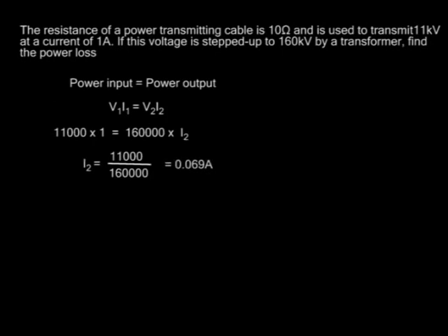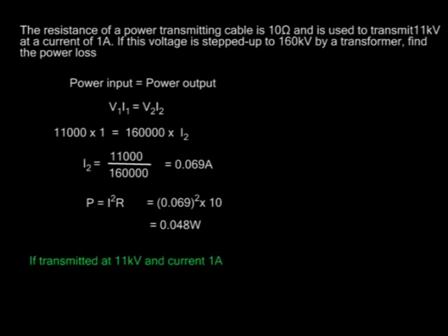That gives us 0.069 amperes. Power loss is given by I²R. If we multiply that, we get 0.048 watts. Now suppose the power was transmitted at 11 kilovolts and a current of 1 ampere. Let's find power loss. Power loss is given by I²R. 1 squared times 10 gives us 10 watts. This shows that when the voltage is stepped up from 11,000 volts to 160,000 volts, the power loss is reduced by over 200 times.